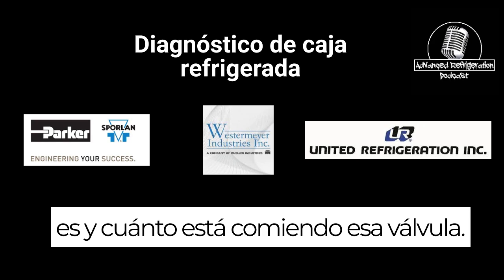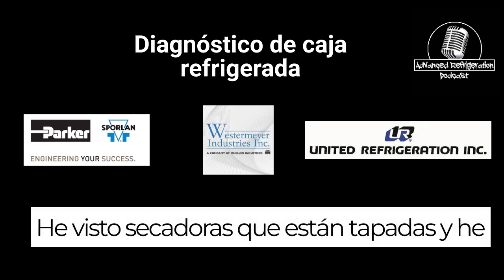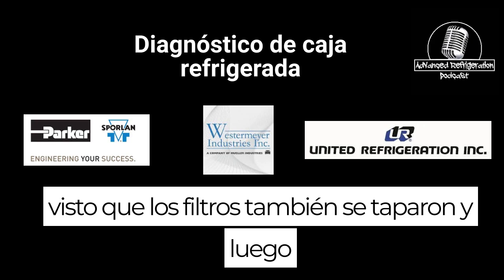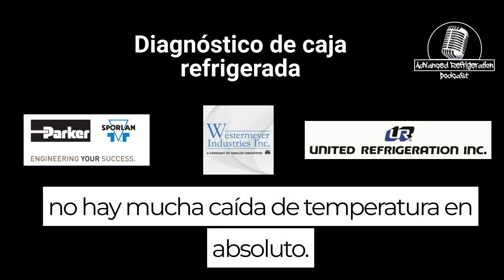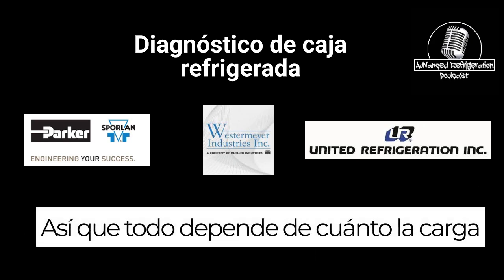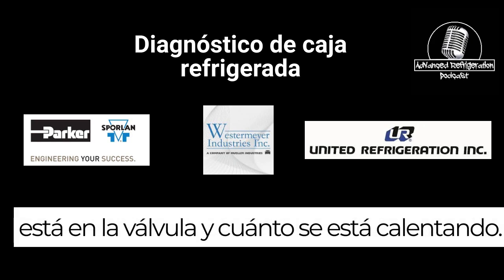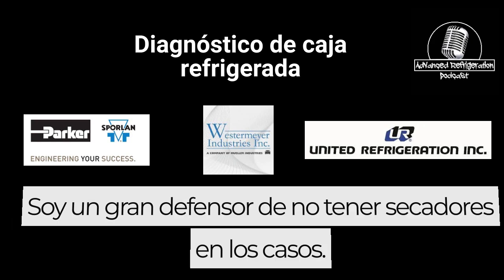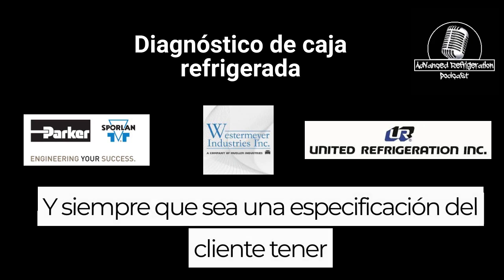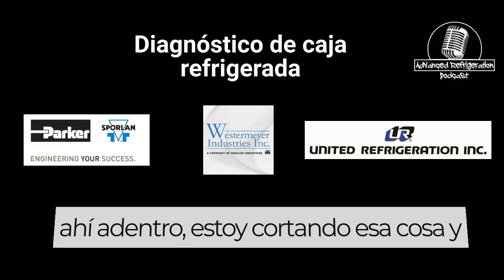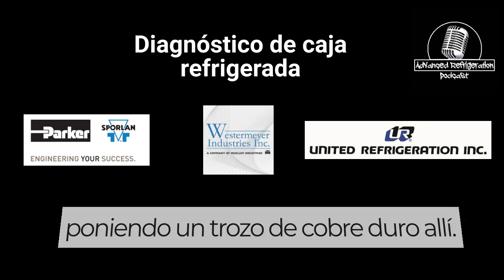And how much that valve's feeding. I've seen dryers that are plugged, and I've seen the strainers be plugged also, and then there's not very much temp drop at all. So it all depends on how much the load is on the valve and how much it's feeding. I am a big proponent of not having dryers in cases. As long as it's not customer spec to have it in there, I'm cutting that thing out and putting a piece of hard copper there.